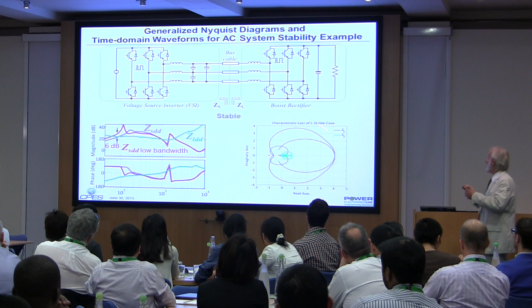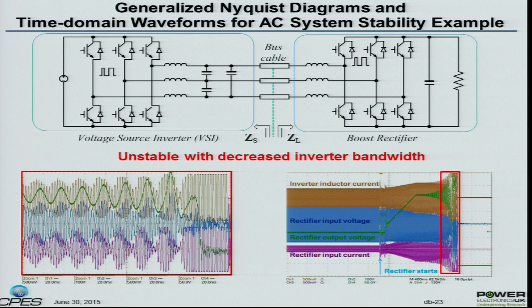If you plot the Nyquist plots, in the stable case with a good inverter and load, you get good behavior at startup, with good voltage regulation and good AC currents. But if you use the inverter with lower bandwidth, one of the Nyquist plots could circle -1, and you go into unstable behavior.